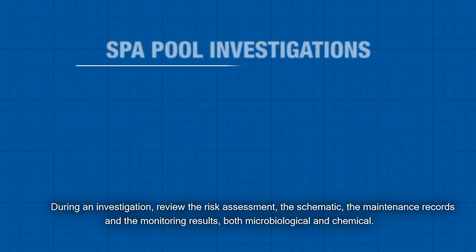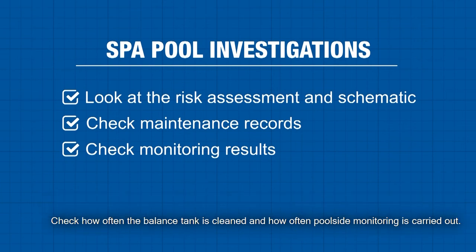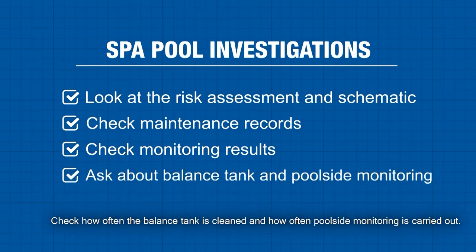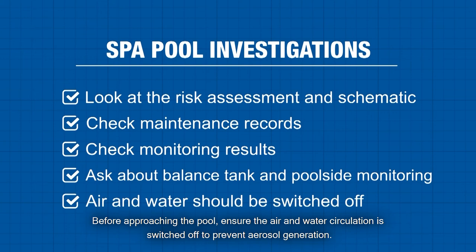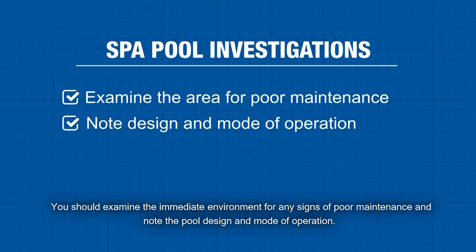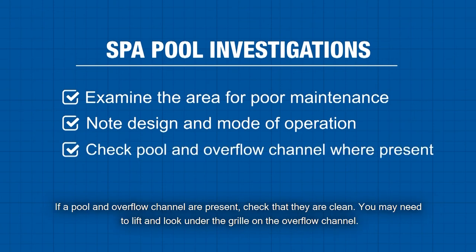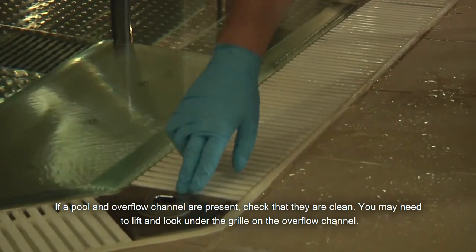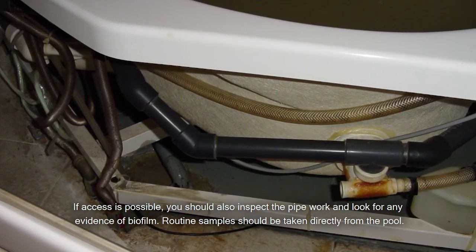During an investigation, review the risk assessment, the schematic, the maintenance records and the monitoring results, both microbiological and chemical. Check how often the balance tank is cleaned and how often poolside monitoring is carried out. Before approaching the pool, ensure the air and water circulation is switched off to prevent aerosol generation. You should examine the immediate environment for any signs of poor maintenance and note the pool design and mode of operation. If a pool and overflow channel are present, check that they are clean. You may need to lift and look under the grill on the overflow channel. If access is possible, you should also inspect the pipework and look for any evidence of biofilm.